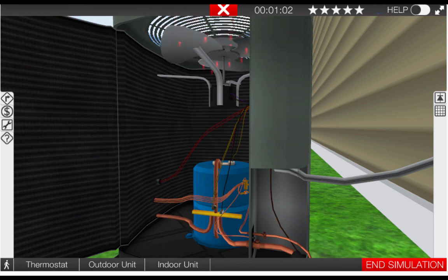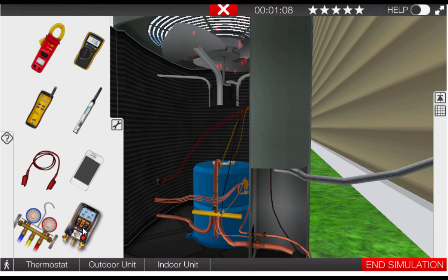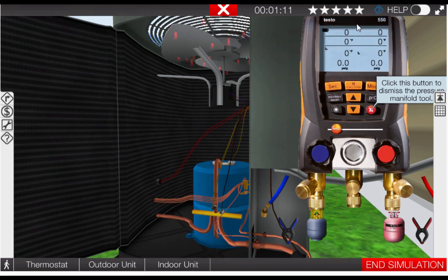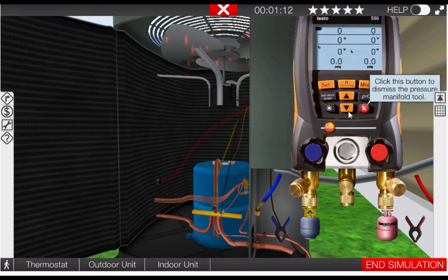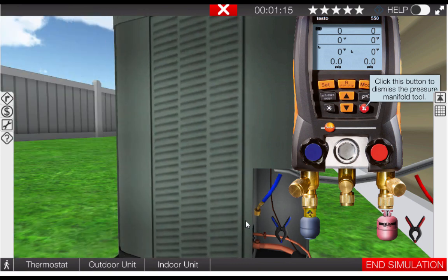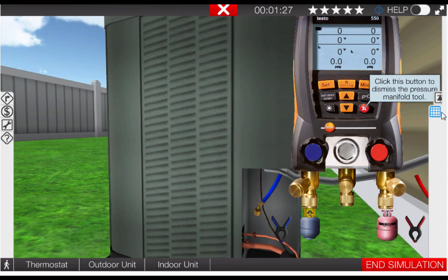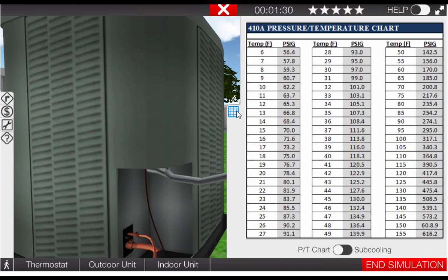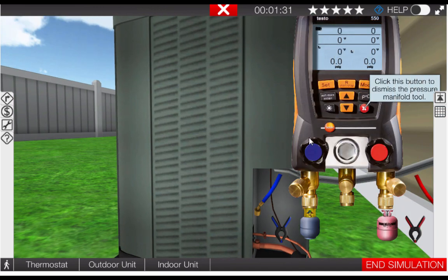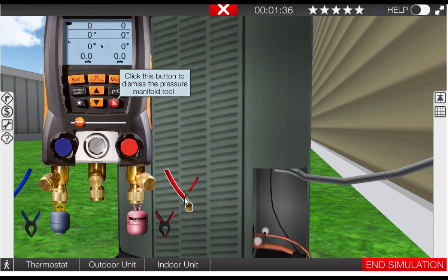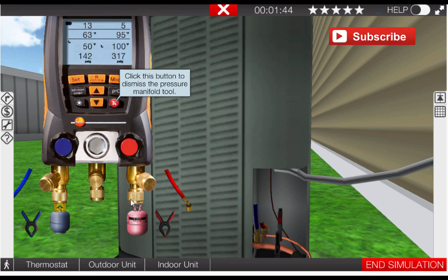Next we want to measure refrigerant pressures in the system. For this activity we're going to use the digital gauge manifold. The digital gauge manifold will do automatic temperature to pressure conversions and use of a temperature pressure chart will not be necessary. However if your preference is to use the analog gauges the temperature pressure chart is always available here on the right by clicking the right icon. This particular heat pump uses R410A refrigerant. So we're going to attach the two hoses, the red hose to the liquid line service port and the blue hose to the suction line service port.